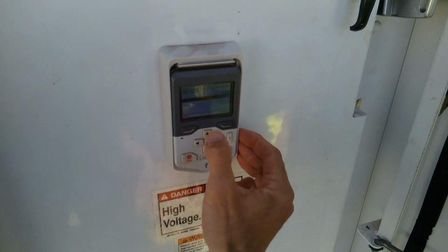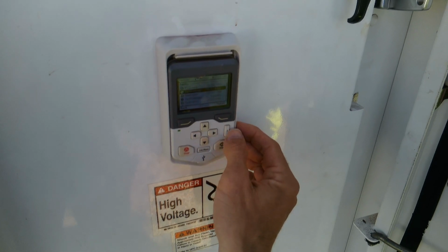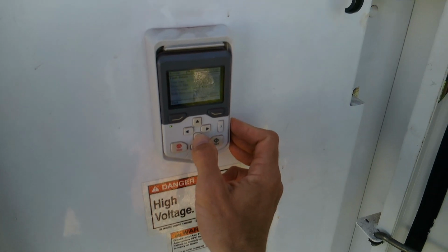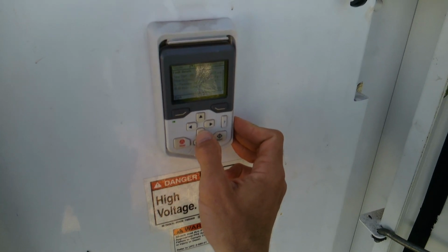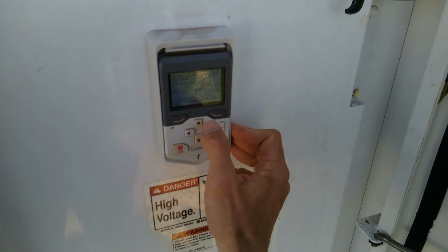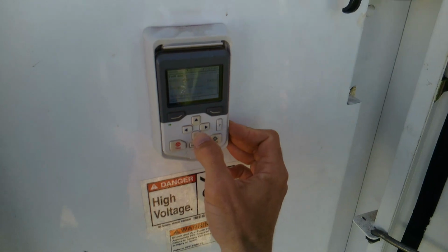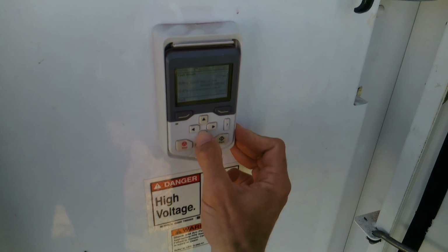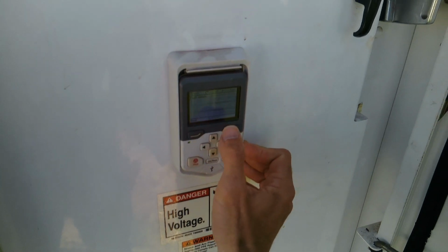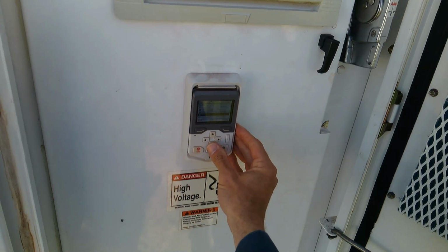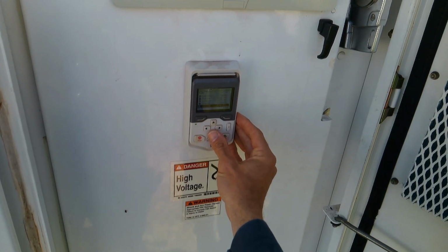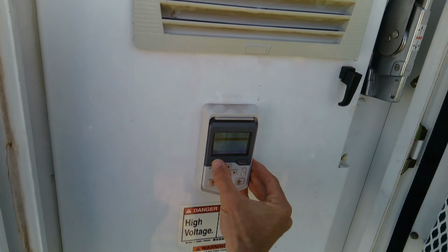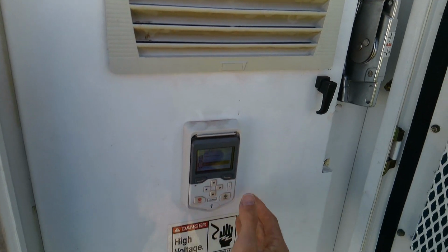Those are all the times it's shut off. Details. It was running fully loaded. Yep, fully loaded, and then it had an earth leakage, this morning, yesterday. And that's it. No other faults or events. So, earth leakage.